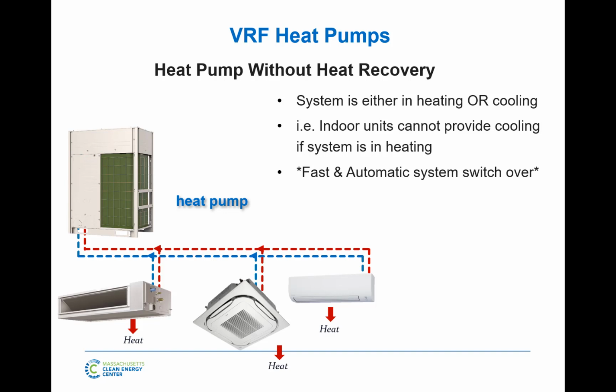There's all sorts of algorithms that different manufacturers have as to how you program that. Well, when do you switch over? Do you wait until there's much of a difference, a small difference? Is it an average? There's all sorts of ways of doing that. You can even make one count for more. This is the boss's office, so if that person wants heating or cooling, they get heating or cooling. You can always weigh things like that. So two main differences between this and a chiller fan coil system is that there's usually multiple systems in the building, and they switch over automatically. So on a warm December day, you'll get cooling. Whereas in a regular two-pipe chiller fan coil, you're not getting cooling. If it's warm in December, those chillers have been long gone, off.